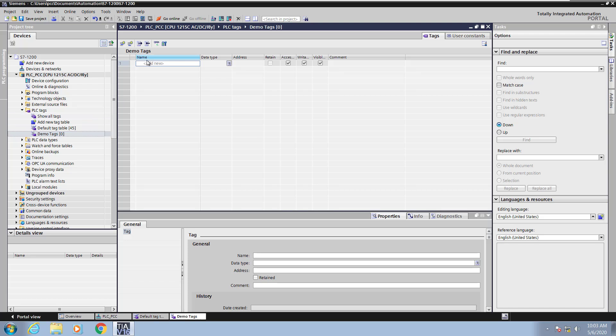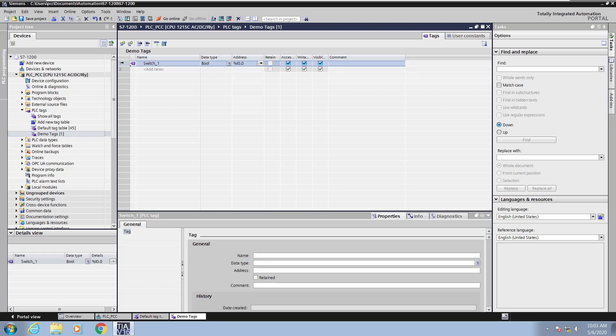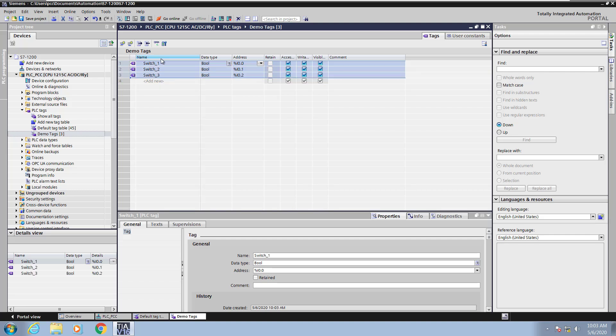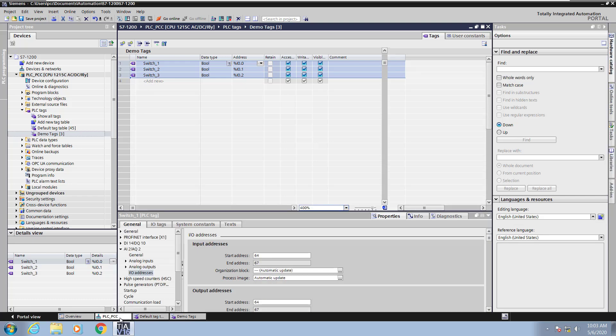I'm going to open up the demo tags table and now I can enter in a tag for the first input on the PLC. I'm going to call it switch1. It defaults to bool and the address of i0.0. There are Excel-like features in the table editor so I can just do an autofill and it will auto-populate and increment the tag names and I/O addresses.